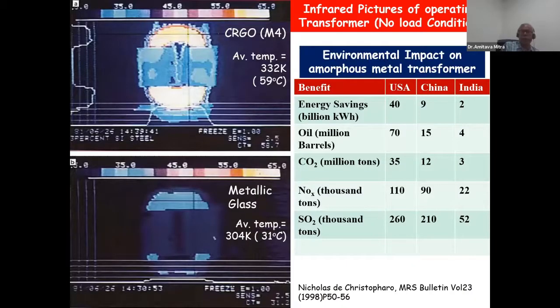What is the advantage of this? If you go for the transformer core, the conventional or crystalline material will heat up to around 59 degrees Celsius, requiring oil for cooling. But in this case, you don't need any oil because the heat is only around 31 degrees. This is a big advantage when you consider pollution to the environment. This type of transformer is also called the green transformer, using these materials.